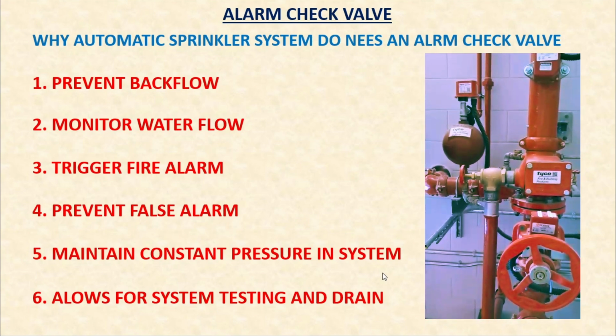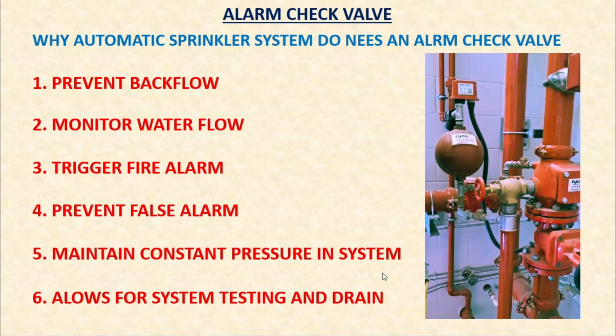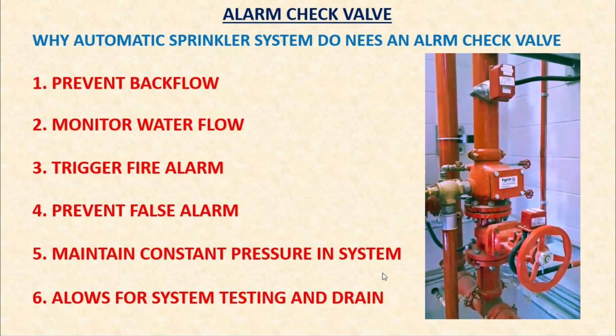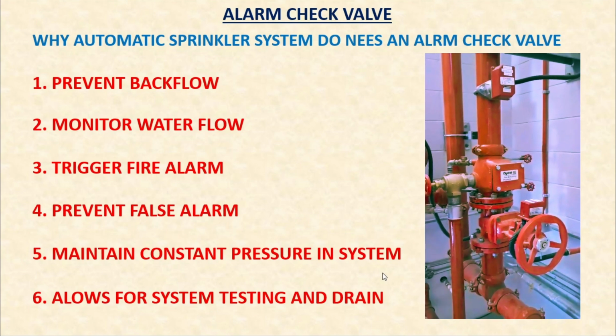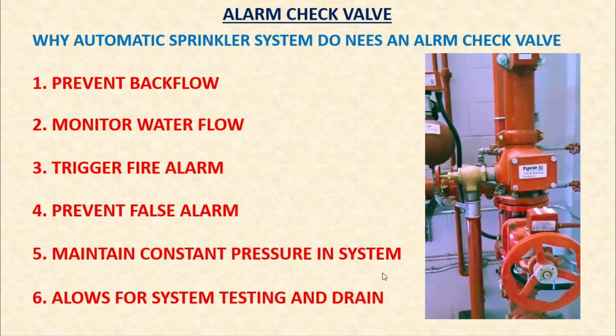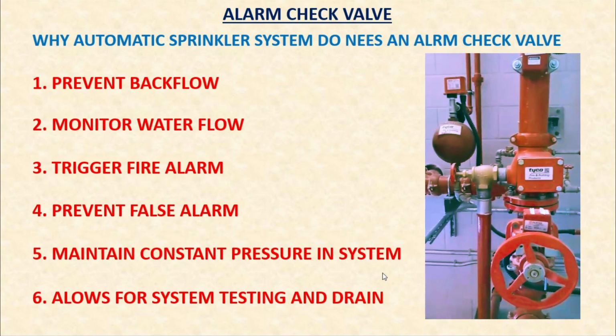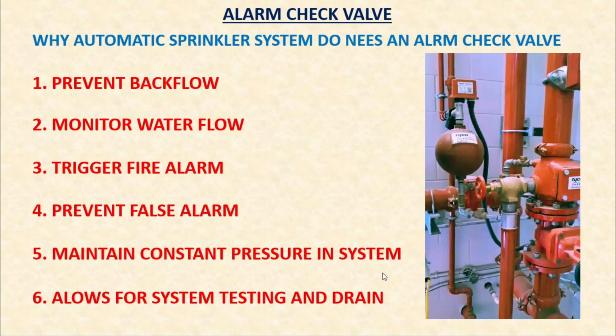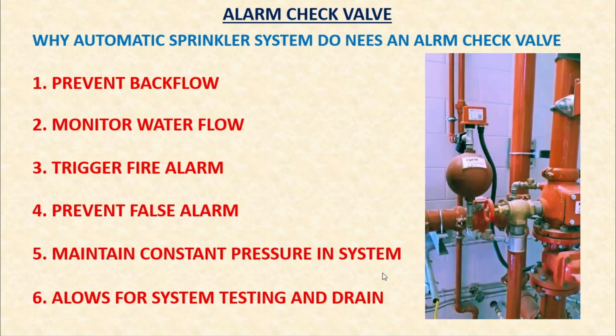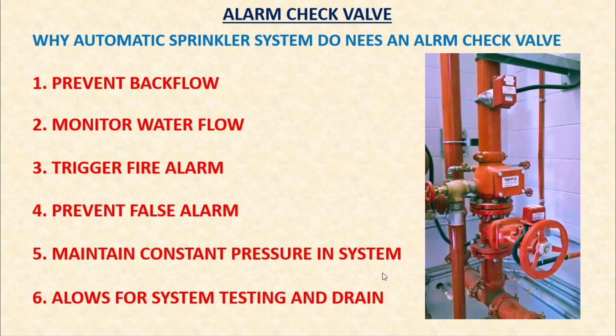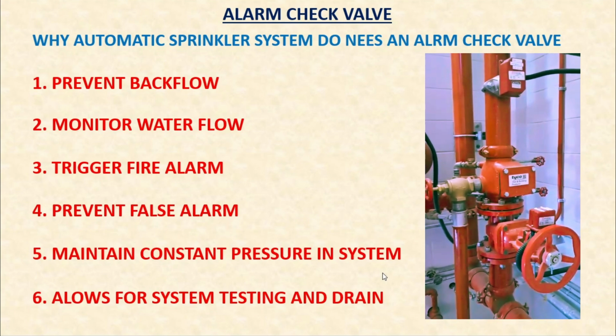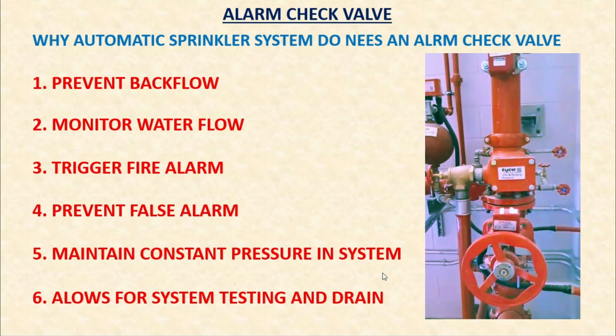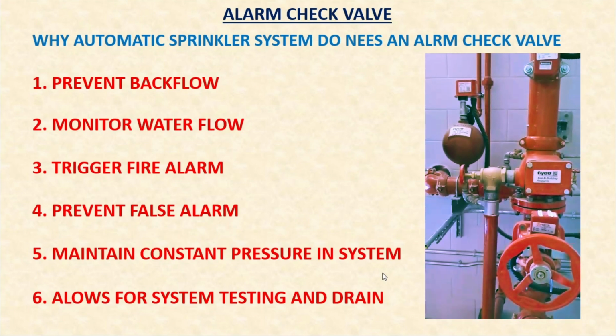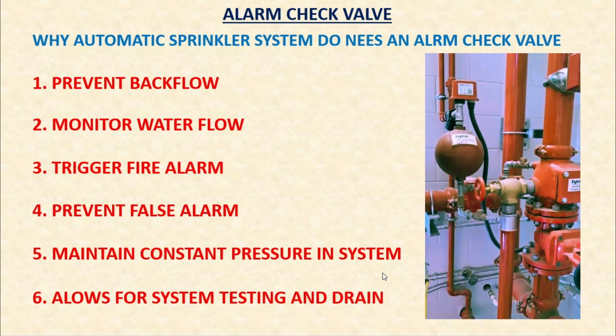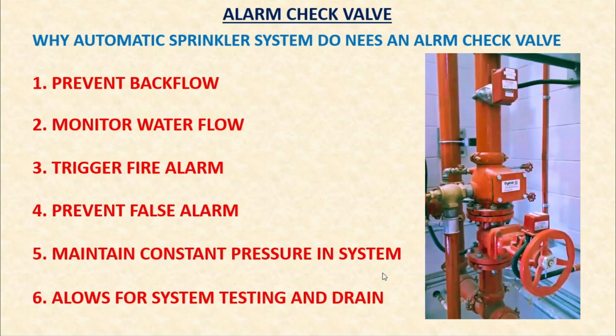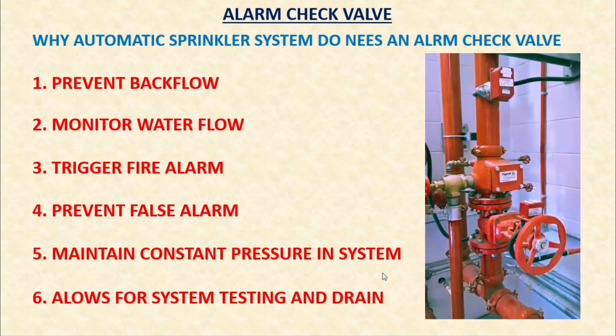The fourth thing is it prevents false alarms using a retard chamber. So you know that this valve includes a retard chamber which prevents the alarm from being triggered by minor pressure fluctuations in the water supply system. The next is to maintain constant system pressure. So you know that the alarm check valve maintains the system pressure, on the higher side, constant. Suppose your pressure is set to 8 bar, it will not allow the system to fall below 8 bar because we have a clapper sitting in the check valve which prevents the water flowing backward.